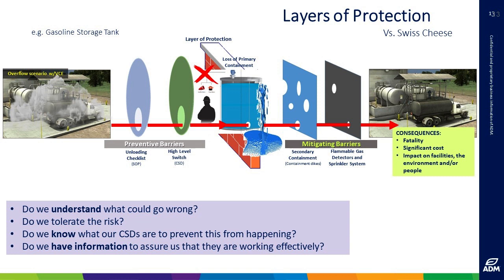So in our hexane processes, we have pumps interlocked with bonding and grounding cables, where if you pull a truck up with hexane, you can't turn the pump on until you connect the bond to the truck. You connect it over to the grounding bar here. There's a logic system that gives the permission for the pump to run for that reason.